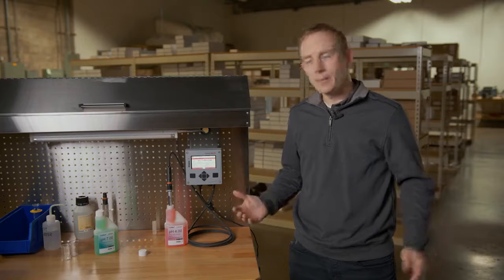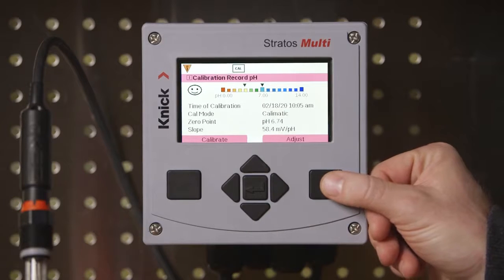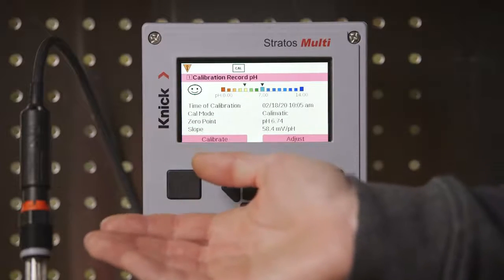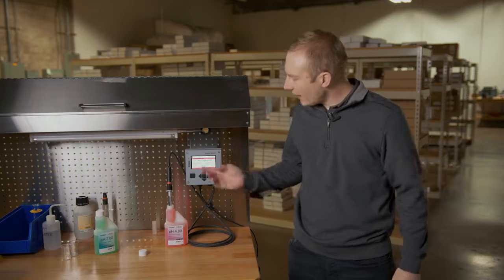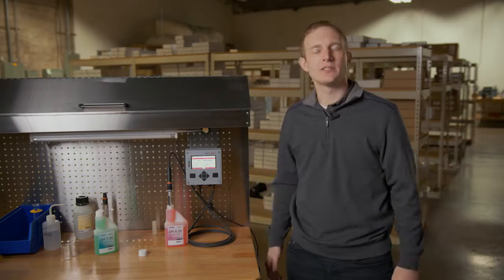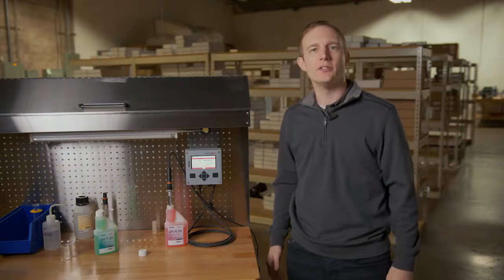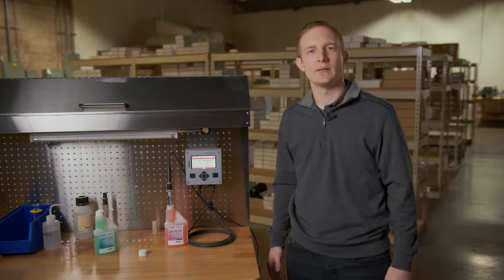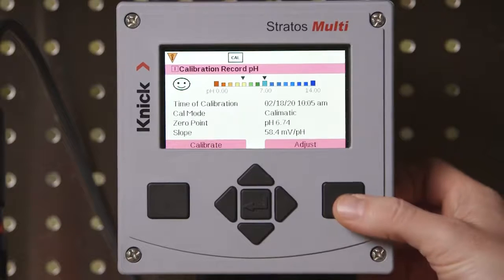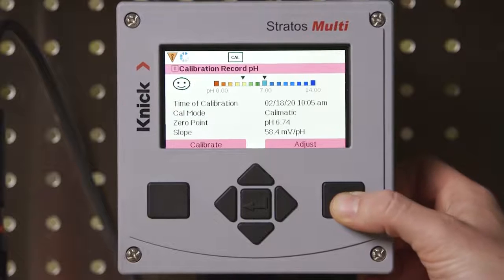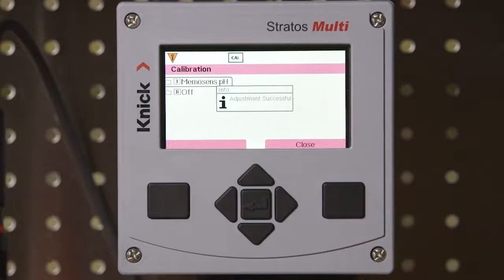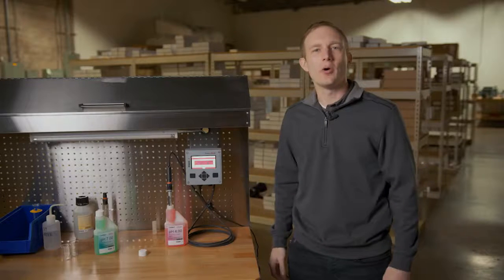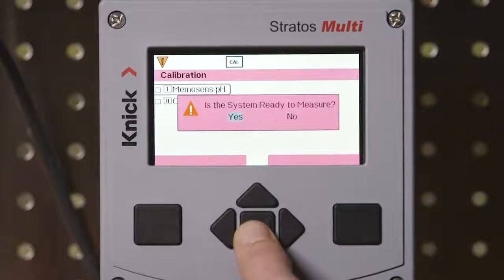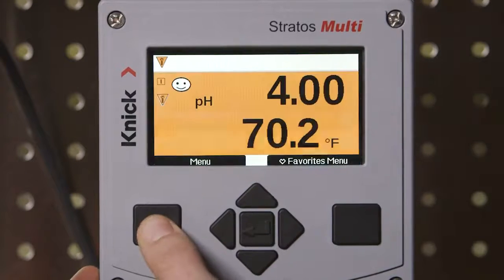Please note that only by selecting the Adjust button will the data be written to the head of the sensor. Selecting Calibrate here will not make adjustments to the sensor and will return you to the main calibration screen. We will select the Adjust button to make the changes to our sensor and finalize the calibration process. We are now ready to go online with our measurement or disconnect our calibrated sensor for future use in the field.